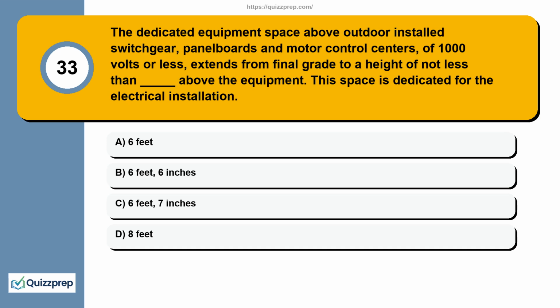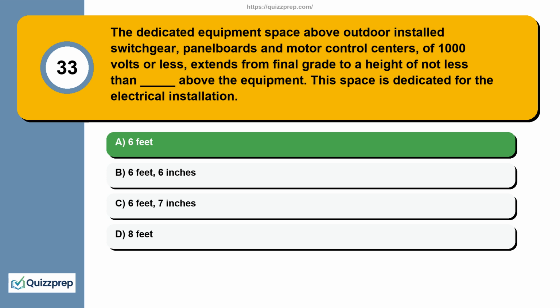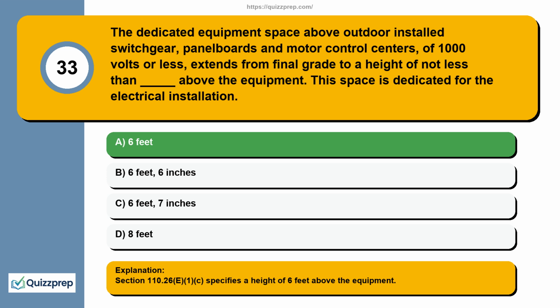Question 33. The dedicated equipment space above outdoor installed switchgear, panelboards and motor control centers of 1000 volts or less extends from final grade to a height of not less than what above the equipment? This space is dedicated for the electrical installation. 6 feet, 6 feet 6 inches, 6 feet 7 inches, 8 feet. Section 110.26(E)(1)(c) specifies a height of 6 feet above the equipment.